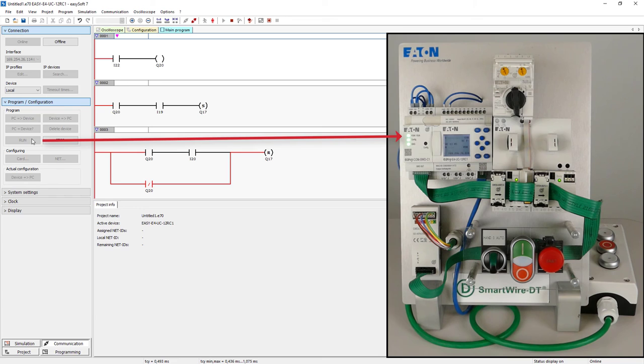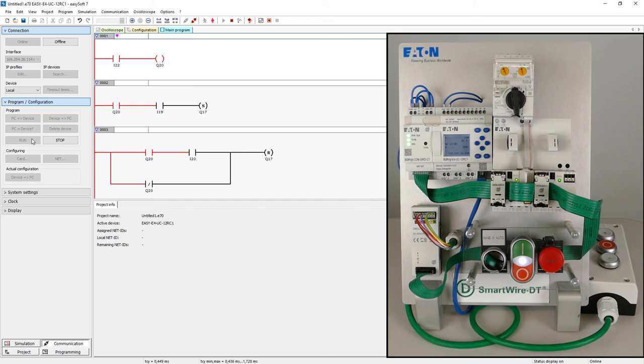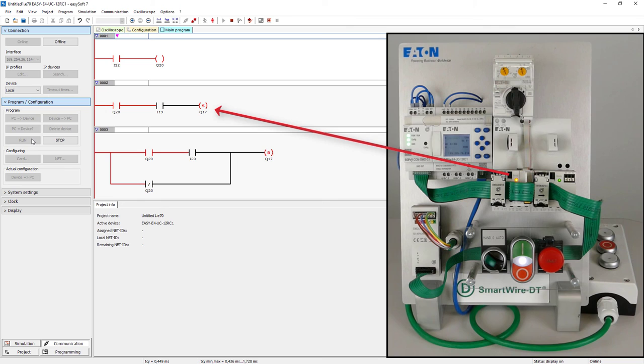Now let's move on to the program test. With the hand pre-selection on the selector switch the white indicator light will illuminate. Now the contactor can be switched on via the green on button and switched off again via the red off button. If the position hand is left at the selector switch while the contactor is switched on the contactor switches off.